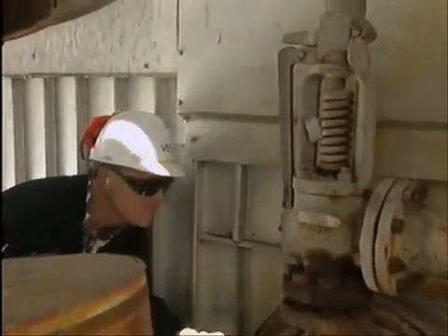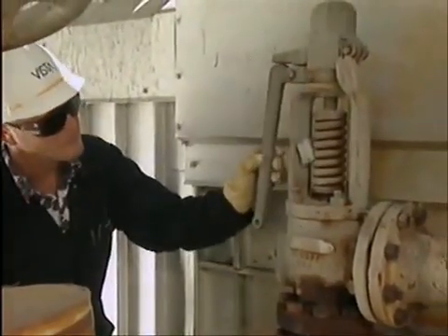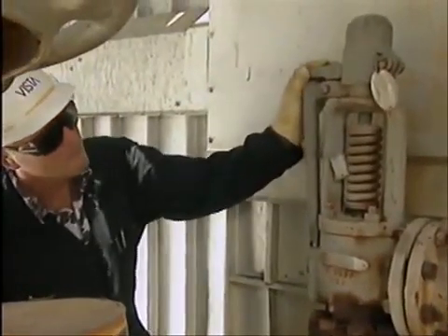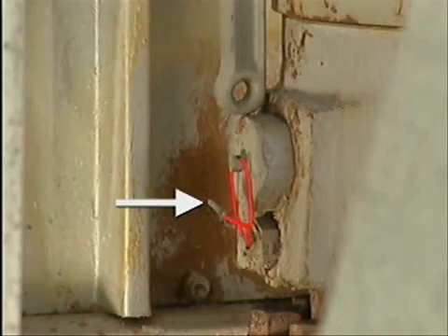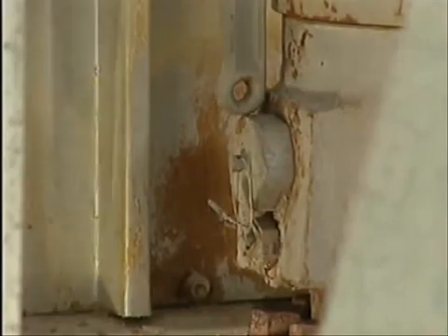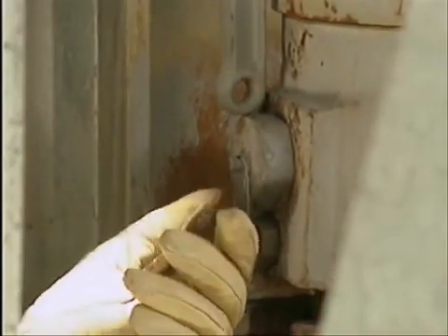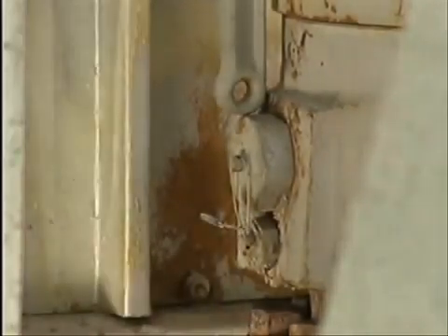Next, proceed with a step-by-step external examination of the different parts of the valve. For this 2-ring huddling chamber safety valve, first check the lock wire on the adjusting ring pins. The lock wire is fastened in place with a metal clip as the final step in the valve reassembly procedure. So the presence of the metal clip is a sign that the adjusting rings should still be properly set for operation. If the metal clip is missing, or if the lock wire has been tampered with, the valve set points may not be correct. Then you must have the valve taken to the shop to check the adjusting ring positions, and if necessary, reset them.